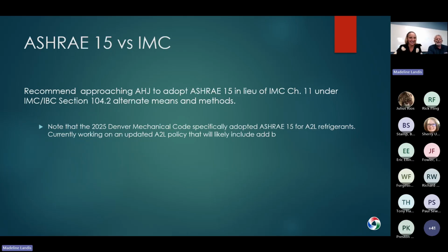So yes, we recommend using ASHRAE 15 versus IMC. Go to your authority having jurisdiction and talk with them. Many of them have already set up policies. Denver, in particular, completely adopted ASHRAE 15 for A2L refrigerants. So that's what I've got to say. Talk to us about some more details if you need to.